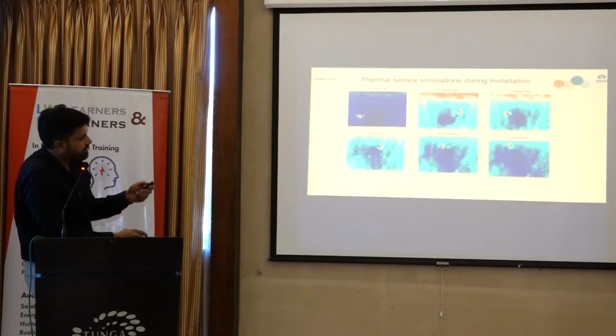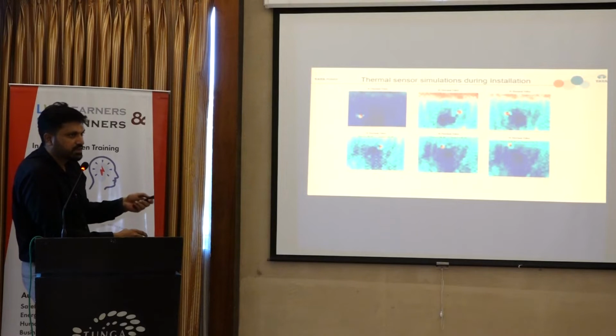The thermal sensors, after we installed, we just simulated them to check how it works. So these are some hotspots which we created manually inside the cable box to check.